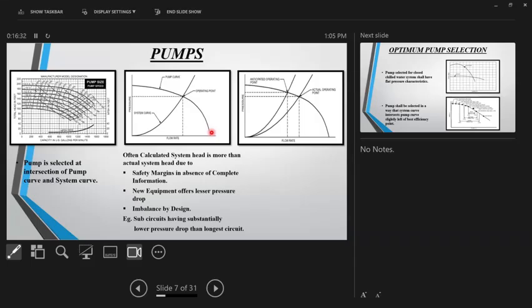A pump curve is nothing but a map or locus of pump operation at various pressures, showing how the pump will behave. As you can see, as the flow rate increases, the pressure developed by the pump reduces. If you see at this location, the flow was less and the pressure was more. If you increase the flow at this kind of point, the pressure reduces. So this is basically an operating envelope, or operating locus, of a pump. Now this pump curve is at a particular speed, let's say 50 hertz, or 60 hertz if it is in UAE. I don't know what the speed is over there, but in India 50 hertz is the synchronous speed. If you run the pump at 50 hertz, you will get an operating envelope like this. If you reduce the pump speed, you would get a parallel curve like this, but it will again follow the same shape. So this is known as a pump curve.